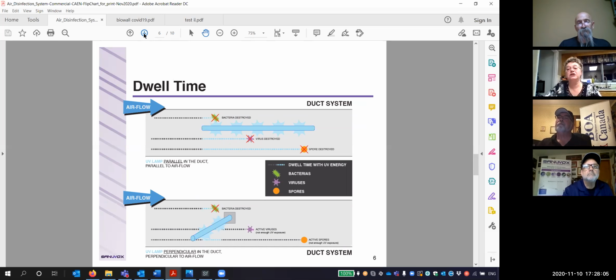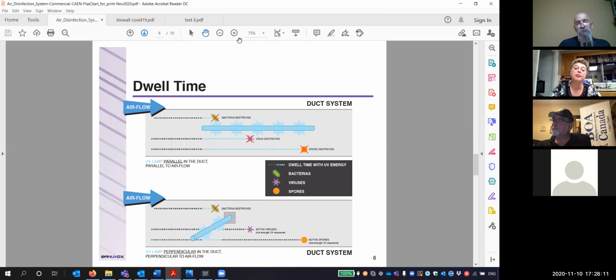So I just want to talk about dwell time and how we destroy COVID-19. With the Sanuvox products, we position all of our torpedoes in the ductwork parallel with airflow. This is really important because we get a longer time period of exposure to this UV. Now, most other UV products out there on the market, they put the units perpendicular with airflow, so really all they're getting for treatment is that diameter of that lamp. With our systems, the lamp is positioned parallel, so you get a nice long treatment.